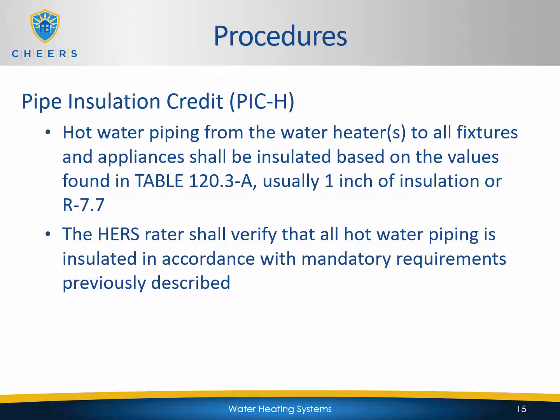The hot water piping from the water heater or heaters to all fixtures and appliances shall be insulated based on the values found in table 120.3-A, which is usually 1 inch of insulation, or R7.7. So the HERS rater shall verify that all hot water piping is insulated in accordance with the mandatory requirements that we previously described. All of it is going to be covered in insulation, including bends and all sections within the walls, with the exceptions for an exterior wall that's already insulated, which maybe doesn't need it because it can have 1 inch of insulation around it. So all those requirements we discussed are what's going to apply to this particular inspection.